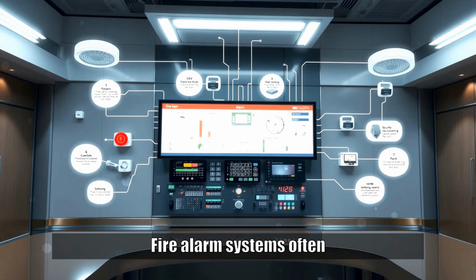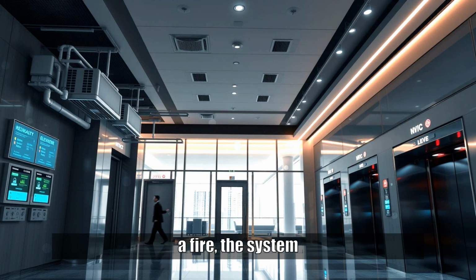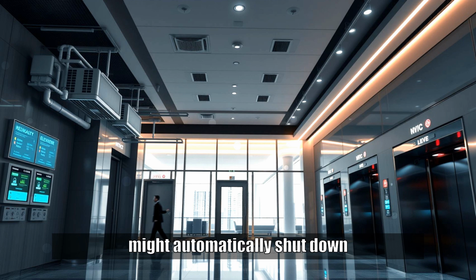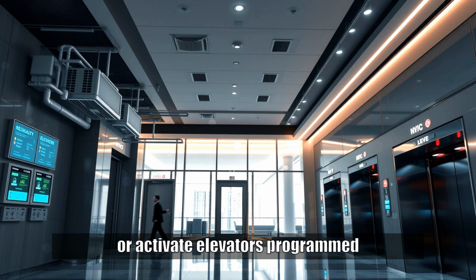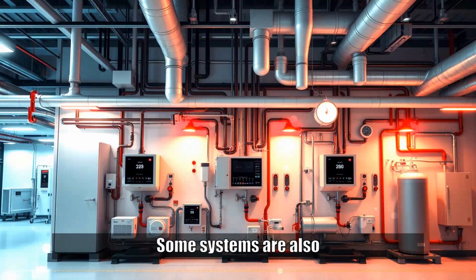Fire alarm systems often integrate with other building systems to enhance response and safety. For instance, upon detecting a fire, the system might automatically shut down HVAC systems to prevent the spread of smoke, unlock doors for evacuation, or activate elevators programmed for emergency recall. Some systems are also tied into fire suppression systems like sprinklers or gas-based extinguishing systems, ensuring a seamless transition from detection to suppression.